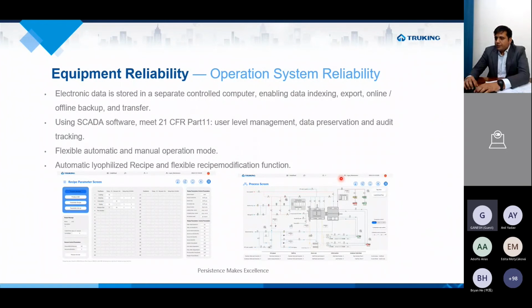Second, the major point about documentation from the equipment reliability point of view: the system is equipped with SCADA software, 21 CFR Part 11 compliant, with an audit trail. Then it has a flexible automatic and manual operation mode, which is sometimes used during maintenance or for providing part of the product recipe. Then electronic data is stored in a separate controlled computer, which enables data indexing, export, online and offline backup and transfer. Automatic lyophilized recipe and flexible recipe modification functions are also provided.